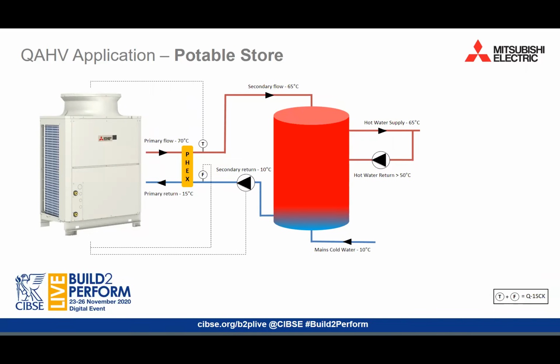So here, the cold mains water is fed into the bottom of the storage vessel. Cold water is then drawn from the bottom of the vessel into the plate heat exchanger using a field supply pump, where it is then lifted to 65 degrees Celsius and supplied back into the top of the storage vessel. Hot water services are drawn from the top of the vessel, with the services return being pumped back into the middle of the vessel. The flow and temperature on the secondary side of the plate heat exchanger is monitored using the Mitsubishi Electric Q1SCK kit. The secondary side pump is controlled by the QAHV using a 0 to 10 volt output to adjust flow rate to ensure the target flow temperature is met on the secondary side.